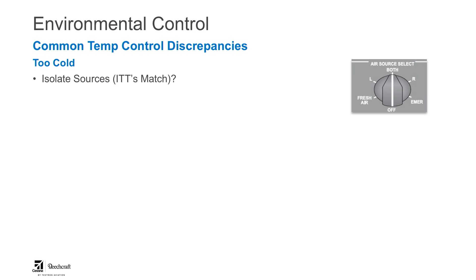All right, again, too cold. Let's see if the ITTs are matching. Maybe we've got something else going on. We can look at the pre-cooler control again. That would be that modulating valve there in green. The service air line going to that has a little orifice in it, and that's to allow it to bleed down when the pneumatic temperature probe shuts off the bleed air.